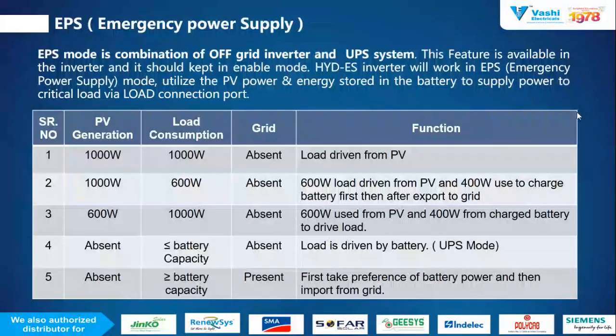Now we are moving to the last mode, EPS mode, which means emergency power supply mode. We have to consider it a combination of off-grid and UPS mode. This feature is available in the inverter, and it should be kept enabled. If you want to use EPS mode, you can easily enable it in the inverter. It applies when grid electricity is not available and PV power is also not available. In this EPS mode, we consider two paths: one is off-grid, and the other is the emergency power supply system.